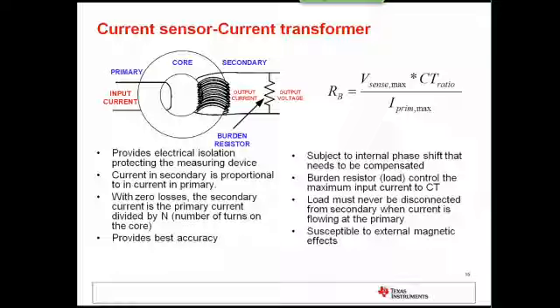However, there are some disadvantages in that it causes a phase shift that has to be compensated for in software, and it could be susceptible to external magnetic effects. If you have a magnet applied to the CT, it could actually cause saturation, which will affect the current readings.